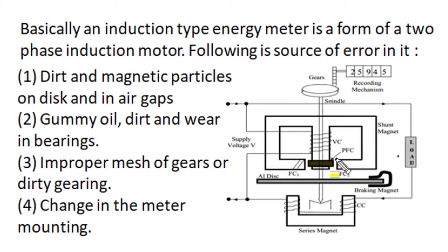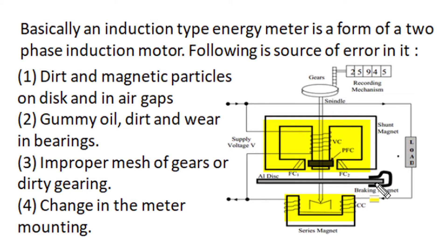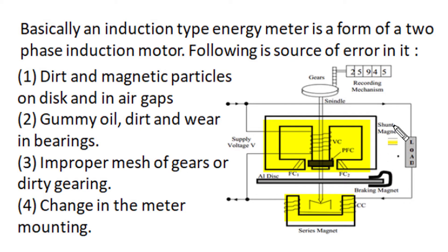It is a form of a two-phase induction motor where voltage excitation in the shunt magnet and current excitation in the series magnet produce two time-varying sinusoidal alternating fluxes around the aluminium disk, and induced EMF circulates current in this disk. Induced eddy currents interact with these magnetic fluxes and produce a rotating torque by spatial design and adjustment. The driving torque in the aluminium disk is made proportional to power flowing in the load through the energy meter.